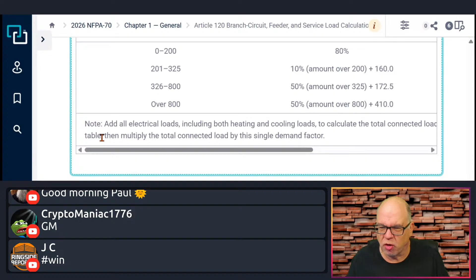I would say 9 times out of 10, they already calculated everything up and gave us a connected load, and then they showed us how they applied 120.88 or 220.88, depending on what code cycle you're in. And that's what they did, that's what I typically would see, okay? So here, it's the total connected load, okay? Add everything up. And then it says, select one demand factor that applies from the table, then multiply the total connected load by this single demand factor.